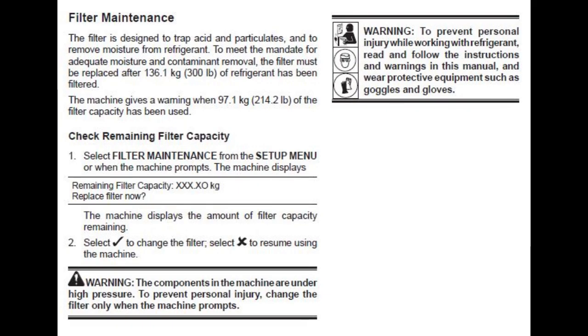Filter maintenance. The filter is designed to trap acid and particulates and to remove moisture from refrigerant. To meet the mandate for adequate moisture and contaminant removal, the filter must be replaced after 136.1 kilograms, 300 pounds, of refrigerant has been filtered. The machine gives a warning when 97.1 kilograms, 214.2 pounds, of the filter capacity has been used.